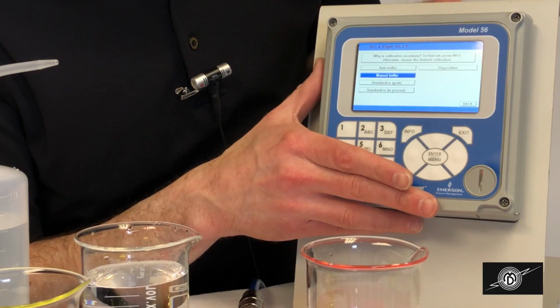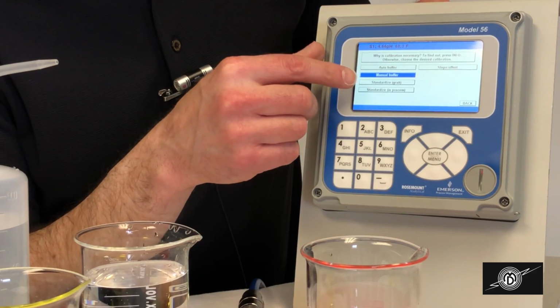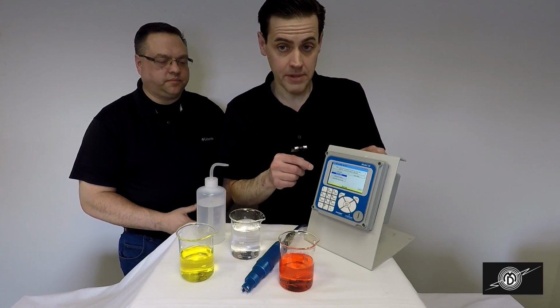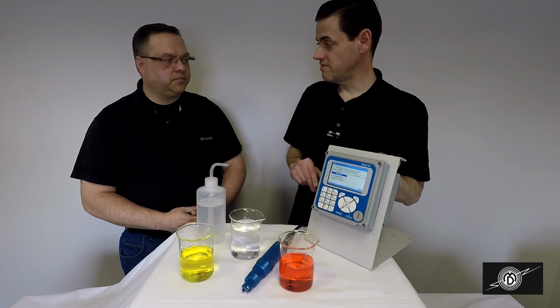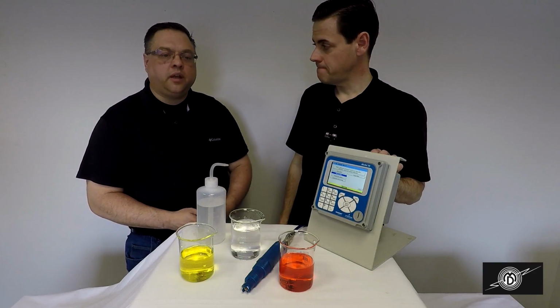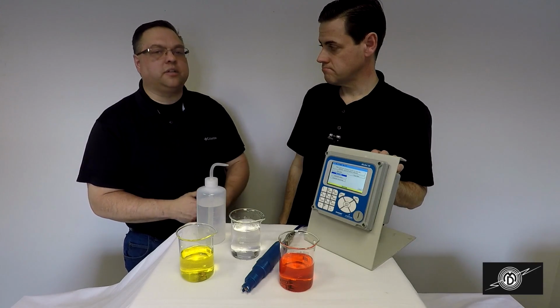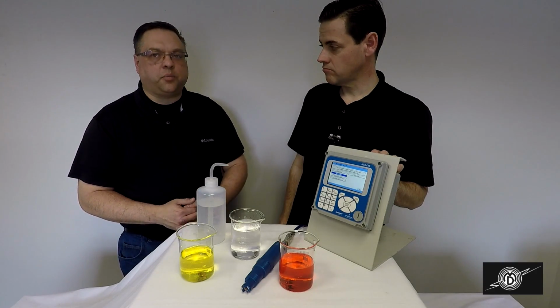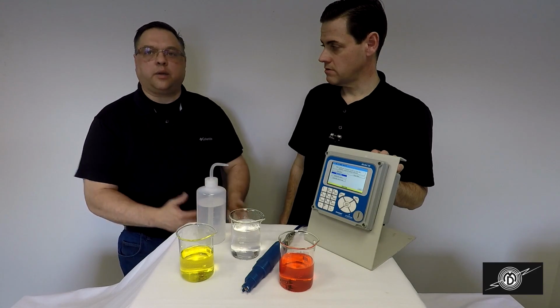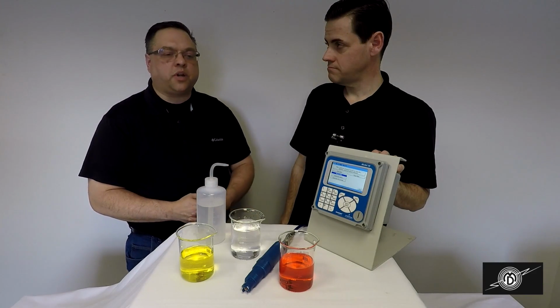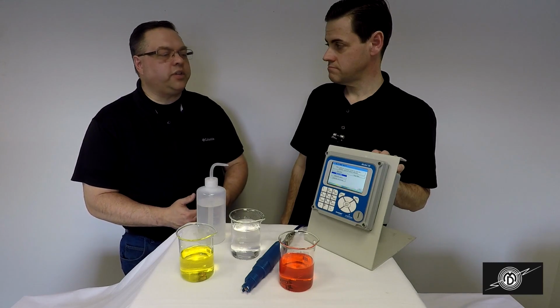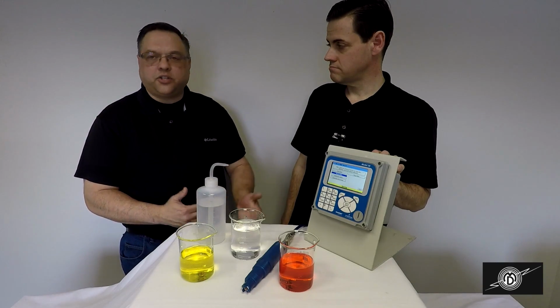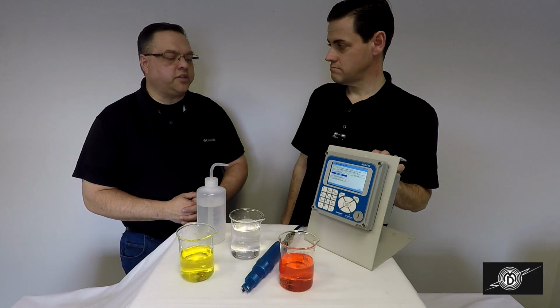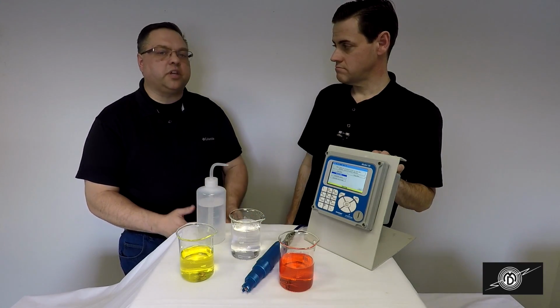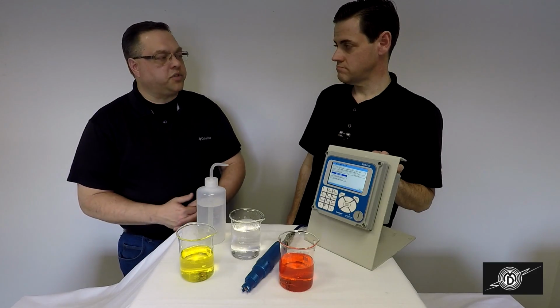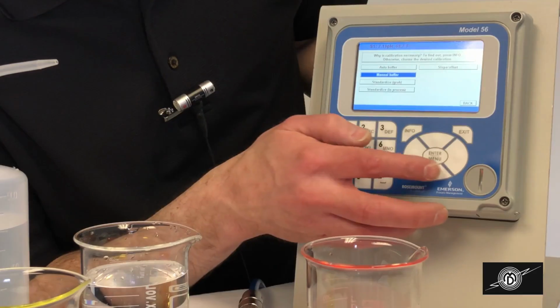So in the calibration menu on this particular analyzer, like many, it offers a selection of automatic or manual calibration. What do you prefer? I prefer to do a manual calibration. With pH probes, you need to be patient when doing the calibration. Automatic calibration is generally a software sequence. After a certain time, it's going to take the value. As probes are used, they tend to respond a little slower and you need a little more patience on the calibration, adjusting to buffer and millivolt signal changes. That's why I prefer a manual calibration, because you can give it a little extra time and give it a more stable reading. Okay, so I'm going to choose manual here.